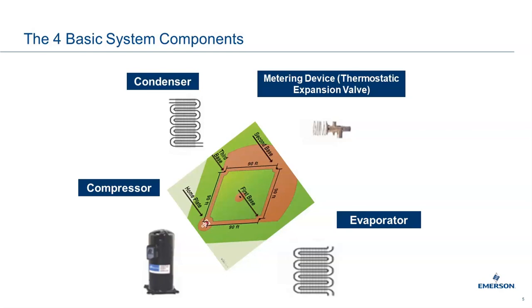I'm going to start with the evaporator. When we talk about the evaporator, we're talking about the component located inside the conditioned space, and it goes from low pressure liquid to low pressure vapor. It also absorbs the heat that's coming through the system, all right? Think of the coil again as a big empty sponge, and the colder it is, the more saturation in there, we can absorb more heat, okay? So that's what we do.